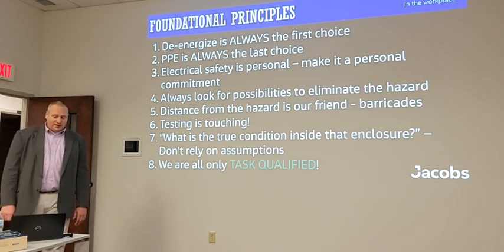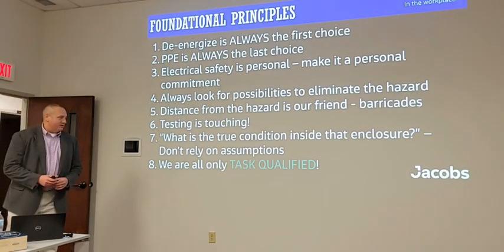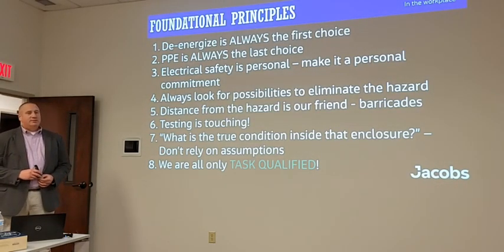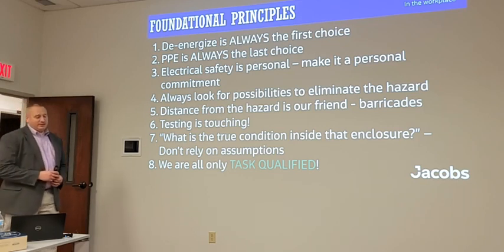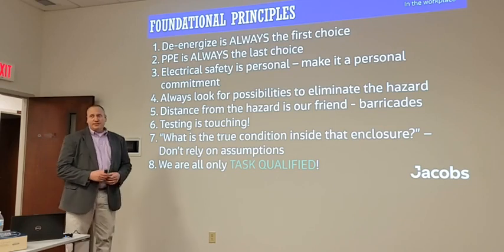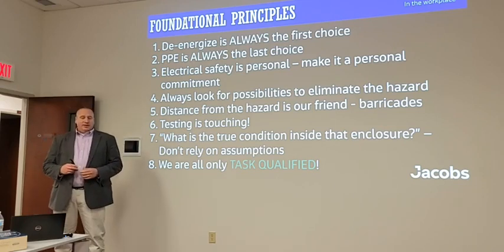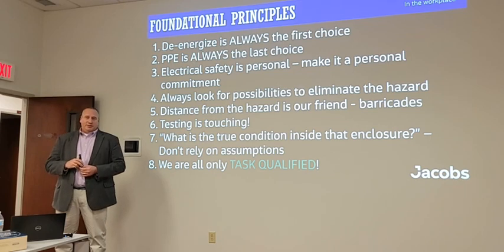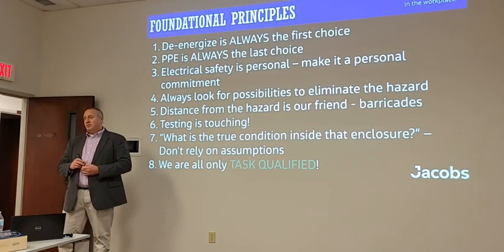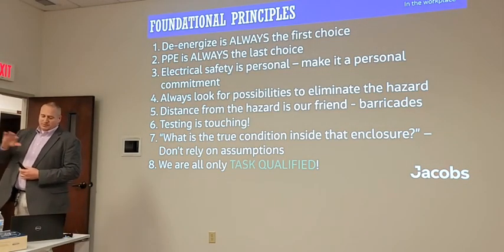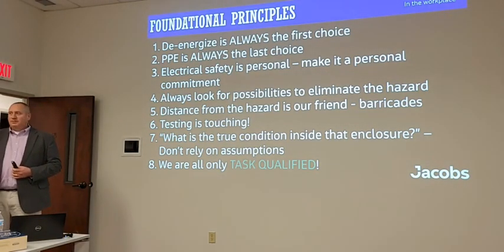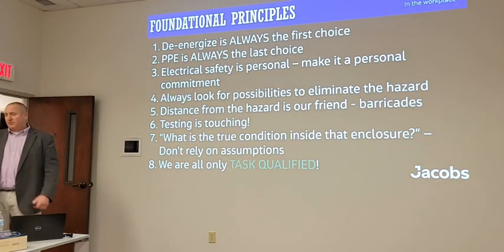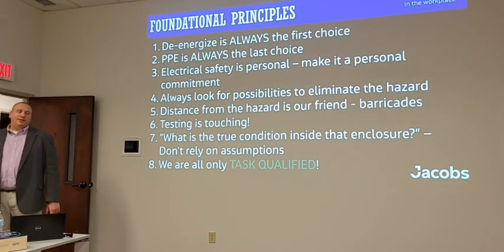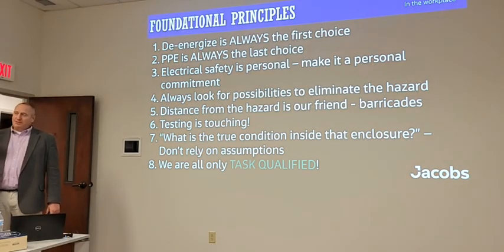And then know that we are all only task qualified, and I kind of talked about that earlier. Don't be afraid to speak up if something seems unfamiliar. One of the learning moments for me as a young engineer was going around and collecting the information for the arc flash analysis, and there's some 480 volt MCCs at a particular wind tunnel test facility, and I didn't know a whole lot about them. In most scenarios, I'd walk up and open the door and get the nameplate data off of them, the settings, and so I was going to do the same thing for this gear that I'd never worked with, and there happened to be a test running, and I opened one of the doors and I heard the breaker open.